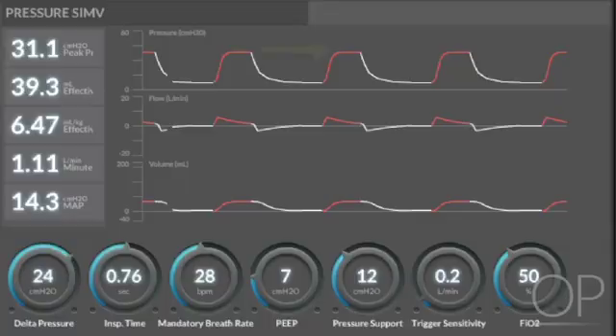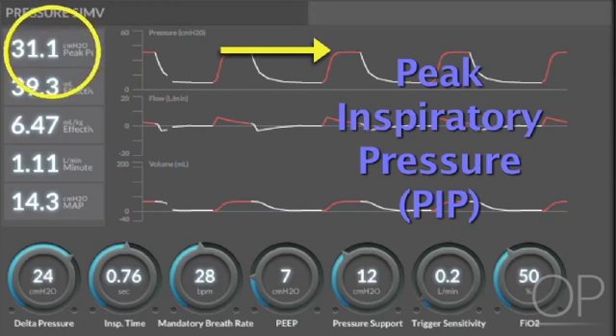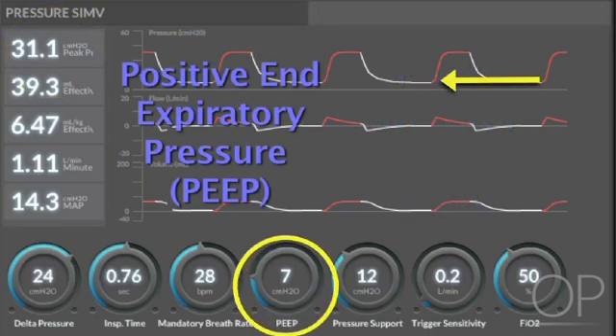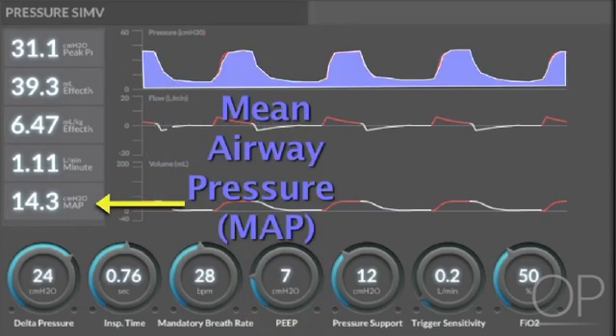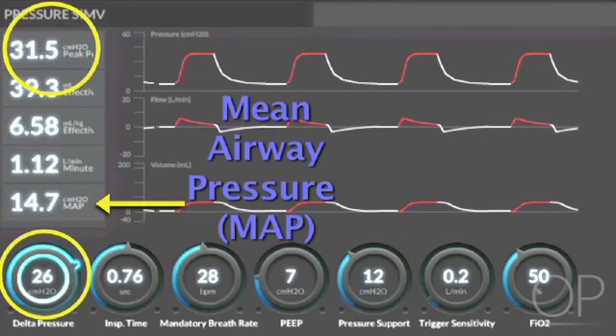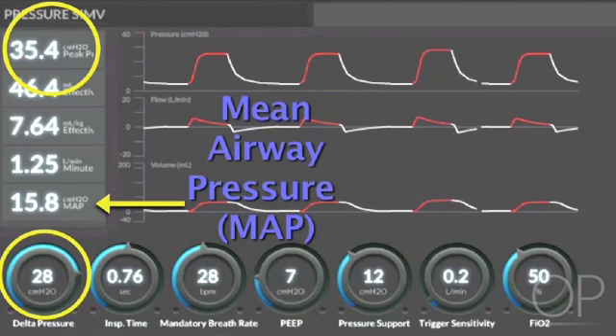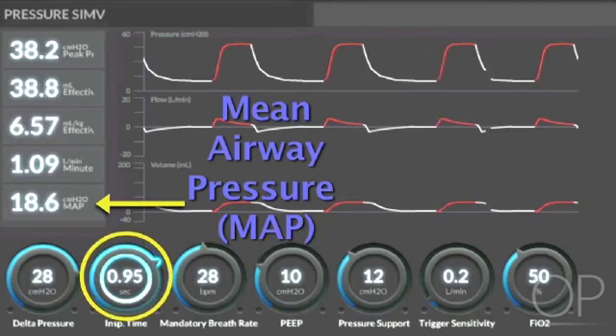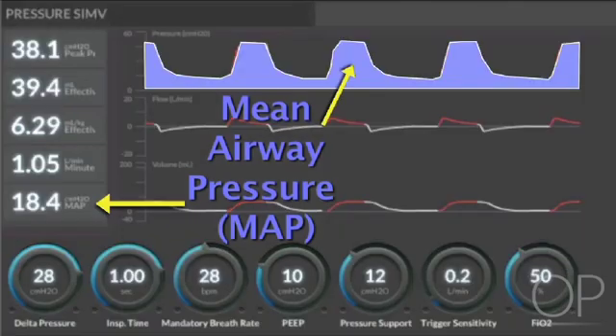Let's review some terminology. There is the peak inspiratory pressure, or PIP, which is the highest pressure the patient normally sees throughout the respiratory cycle. Then there is the positive end-expiratory pressure, which is the pressure present during expiration and prevents the lung from experiencing end-expiratory collapse. The mean airway pressure is the area under the pressure waveform. It's not directly set on a ventilator, but is influenced by other settings — increasing PIP, PEEP, or inspiratory time all increase the mean airway pressure, because all of that increases the area under the pressure waveform.